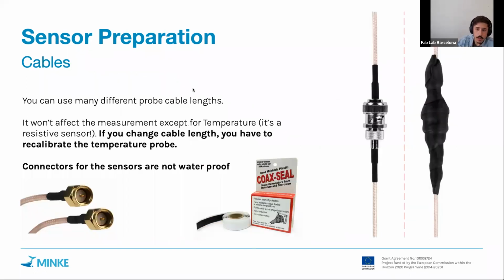So, the famous cables. You will see that all the probes that can be extended, basically beyond 1 meter of cable length, can be extended to either 5 meters, 10 meters, or 30 meters. These cables are very particular and need to be handled with care, and cannot be replaced unless they are the same type of cable, because they have a very particular resistive range. And you will see that we are leaving metal connectors exposed, and these can't be submerged, and it's important that we don't do that before protecting them.